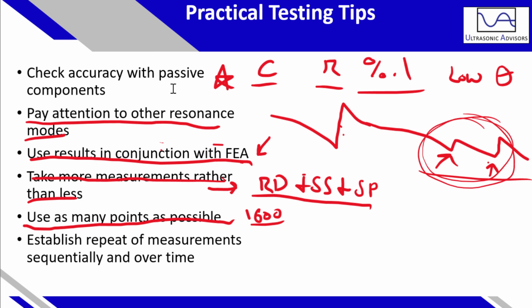So establish repeats of measurements sequentially and over time. Best practice is, whenever you do a measurement, you measure that parameter 3 times. You take an impedance analysis 3 times, as well as over time. After you do system testing, which uses higher voltage, you may see changes in your device performance, perhaps degradation or changing of resonant frequency. So doing these measurements over time helps you understand degradation and change in performance over time, especially if your device has significant assembly steps which do affect performance. You will have changes in performance over time as the ceramic and the interfaces wear in.